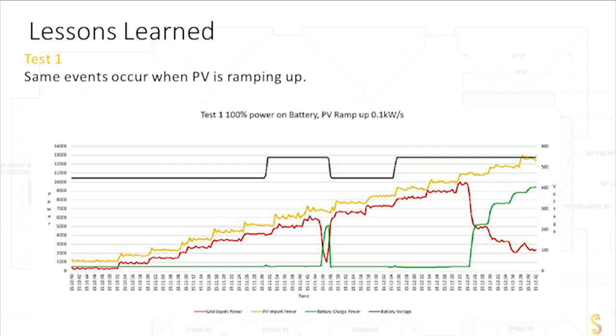And now this entire procedure can be repeated in the other direction, like this graph shows, where the solar starts off really low, because say it's nighttime, and starts to ramp up. And as it ramps up, the battery can turn on, and the inverter can shut it down. It's like there's sort of this dance between the battery and the inverter that goes on and on when we're ramping down or ramping up. And then we can do this much more quickly. We're showing a slow ramp of the solar up and a slow ramp of the solar down.